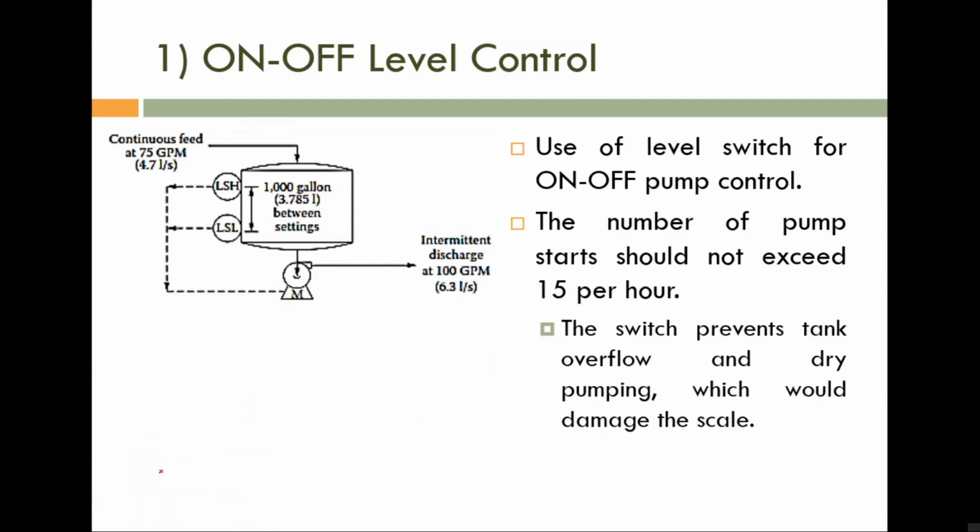So please note here, if due to some reason the number of starts of a single pump is greater than 15, then we have to use one more pump. Okay, one more pump is used. So this is the first pump and this is the second pump, and alternatively these two pumps are started. During the first cycle, the first pump is started, then it is stopped. During the second cycle, the second pump is started, then it is stopped. Like that, alternatively, we have to start the first pump and the second pump.